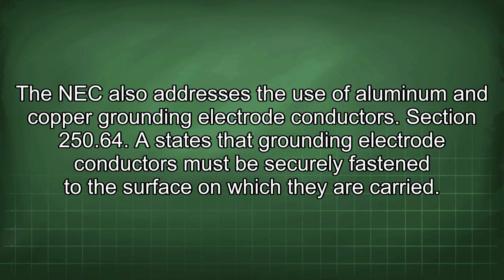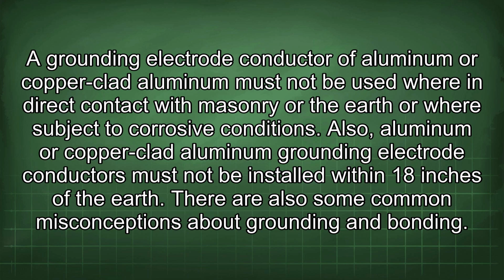The NEC also addresses the use of aluminum and copper grounding electrode conductors. Section 250.64 states that grounding electrode conductors must be securely fastened to the surface on which they are carried. A grounding electrode conductor of aluminum or copper-clad aluminum must not be used where in direct contact with masonry or the earth, or where subject to corrosive conditions. Also, aluminum or copper-clad aluminum grounding electrode conductors must not be installed within 18 inches of the earth.